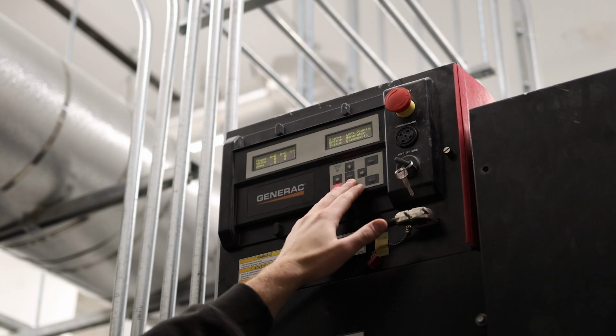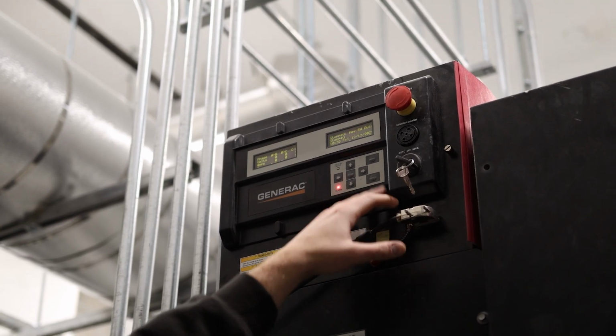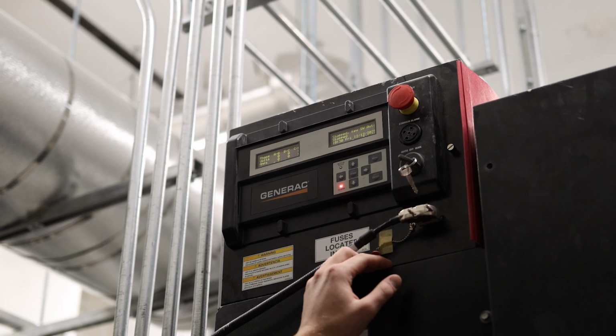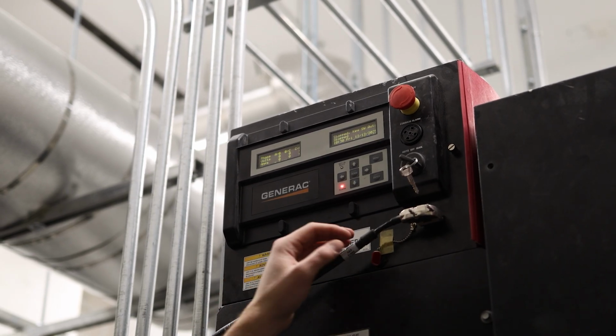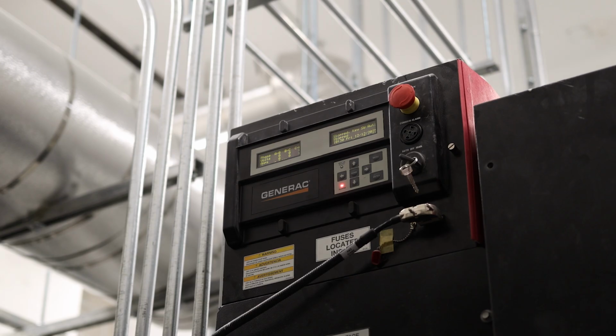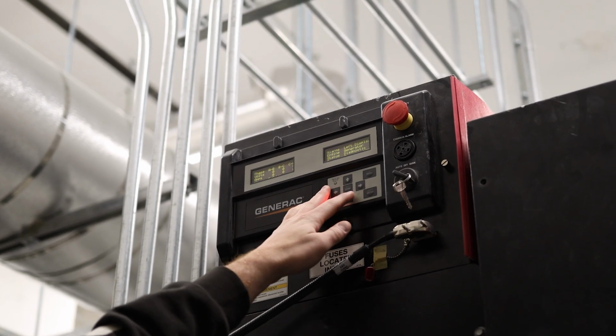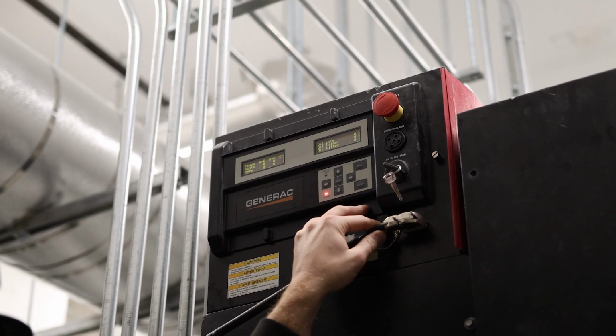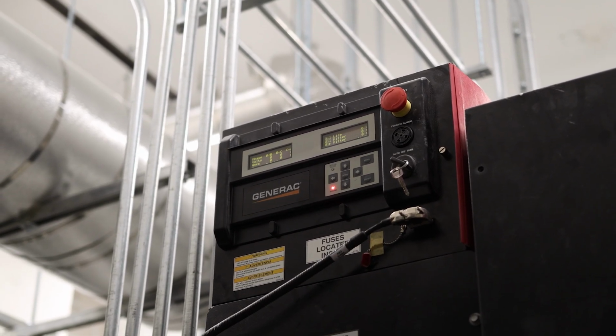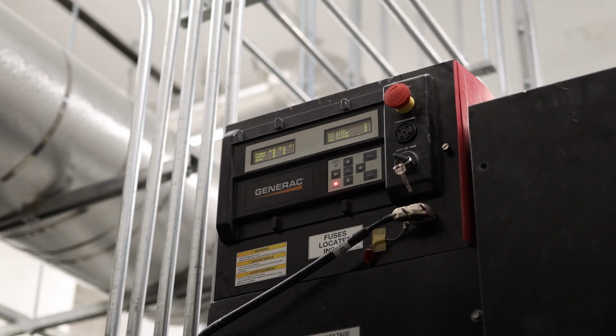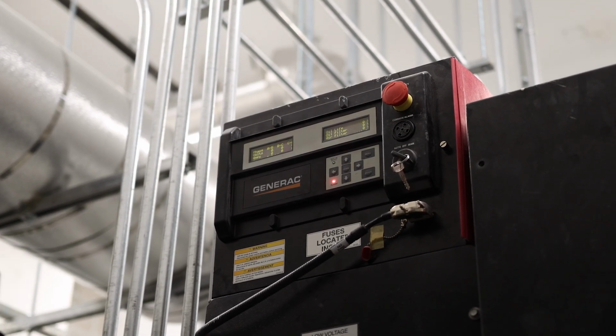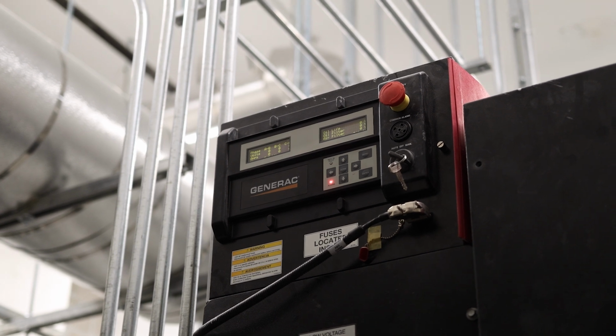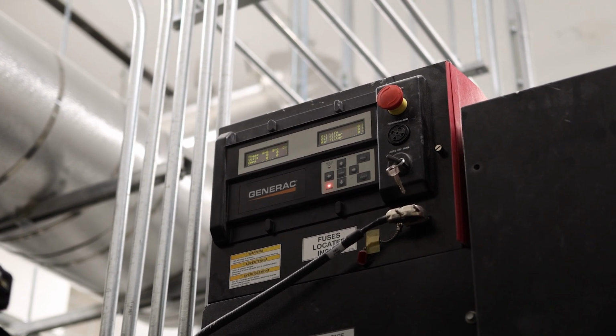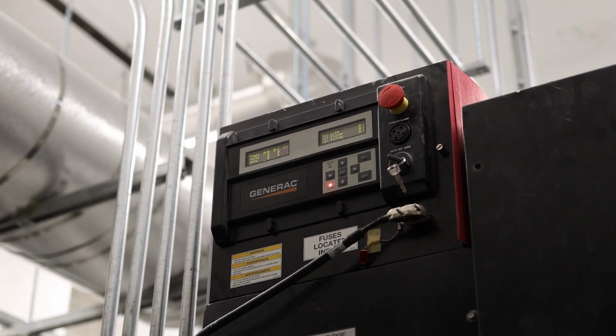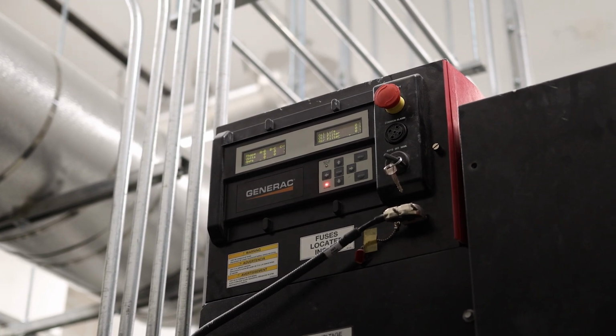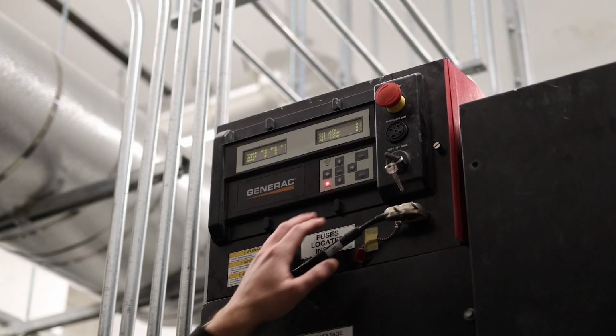Hitting menu again, you can go down two more, and it'll take us to status. Status will show us a baseline of what is going on with the unit: where's the key switch, what's it doing, is it running, is it supplying load, all of that nature. Very bottom is service. This is for service reminders. Generally, we don't bother setting them because they're not actually going to go off before the code required servicing in the majority of cases, unless we had an extreme outage where the unit is running for a prolonged period of time. But realistically, the unit gets serviced before the service reminders would ever run up, and then they just end up being a nuisance eventually.